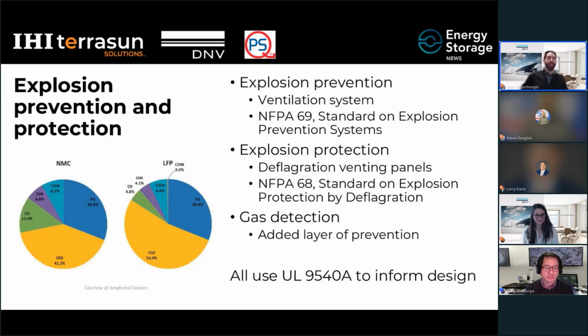Yeah, so UL9540A, much like all the standards, is actively undergoing revisions right now. There are actually revisions out for public comment on UL9540A currently. A lot of the changes involve minor revisions, updates, and clarifications. One big one we're monitoring is revisions to definitions or how testing is performed on containerized BESS units. We're seeing a lot of shipping-style containers, large units that have battery modules slotted into them, and it's not entirely clear what the unit-level definition is for these. So there are clarifications being proposed to determine how these large units should be tested and what should be required of those tests.